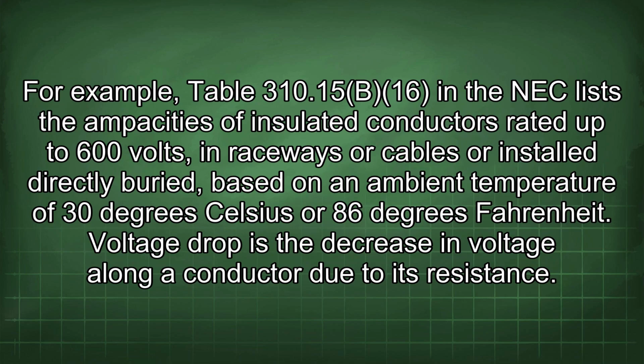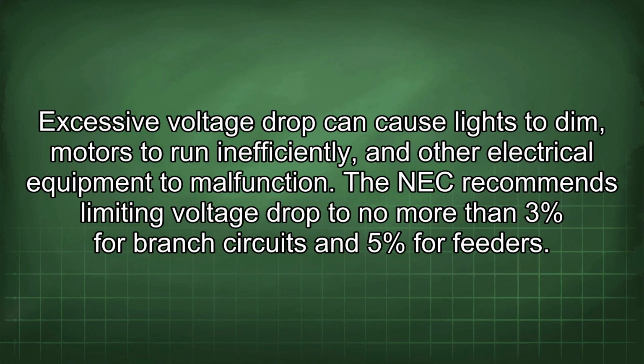For example, Table 310.15(B)(16) in the NEC lists the ampacities of insulated conductors rated up to 600 volts in raceways or cables or installed directly buried, based on an ambient temperature of 30 degrees Celsius or 86 degrees Fahrenheit. Voltage drop is the decrease in voltage along a conductor due to its resistance. Excessive voltage drop can cause lights to dim, motors to run inefficiently, and other electrical equipment to malfunction. The NEC recommends limiting voltage drop to no more than 3% for branch circuits and 5% for feeders.